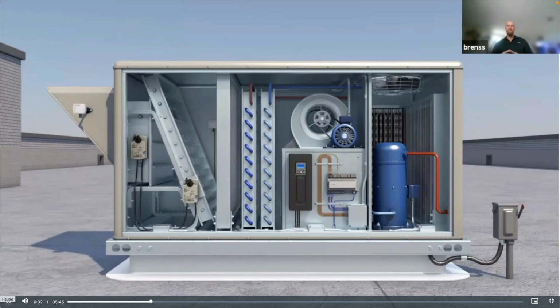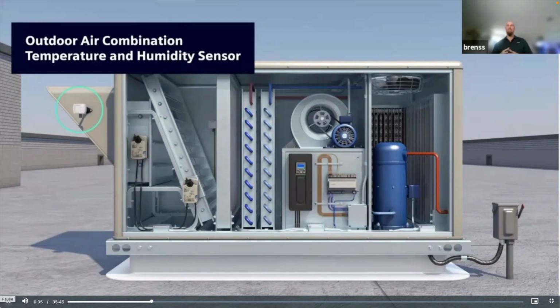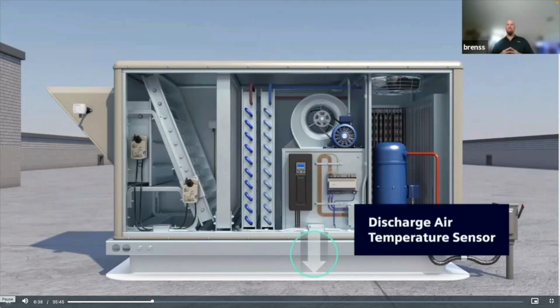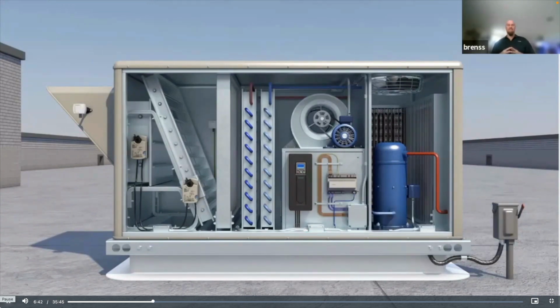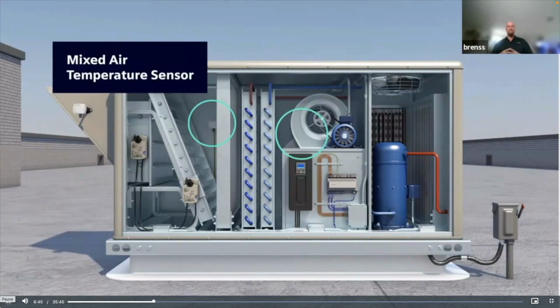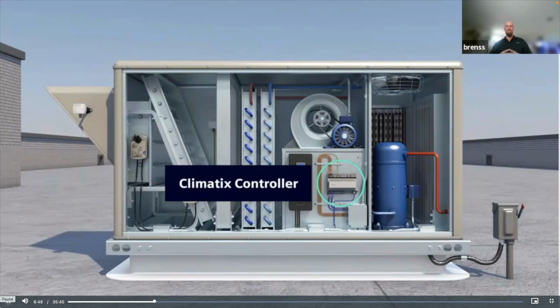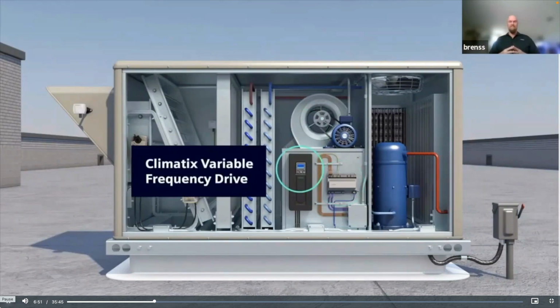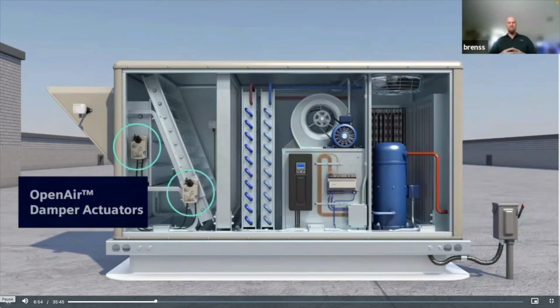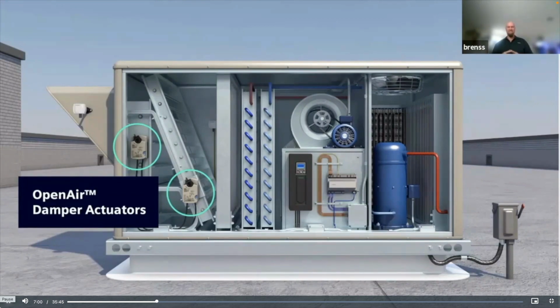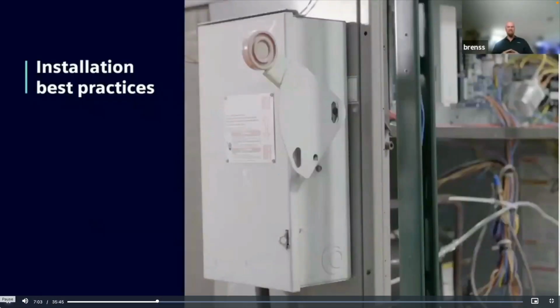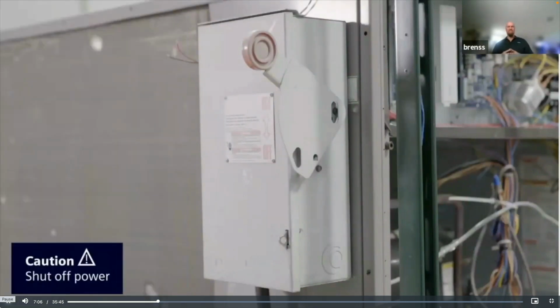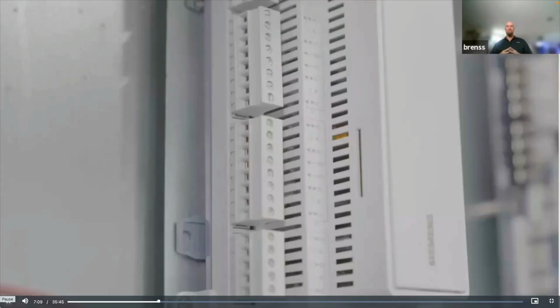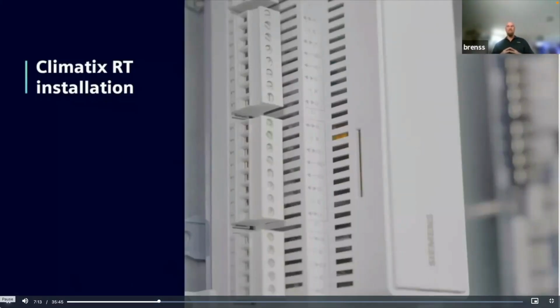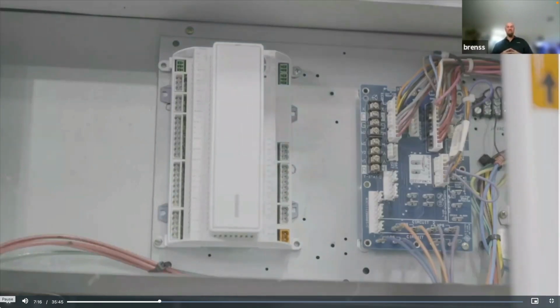Here are the mounting locations for the outdoor air combination temperature and humidity sensor, and the discharge air temperature sensor. Depending on the configuration of your rooftop unit, the mixed air temperature sensor may be located in different areas. The Climatix controller is located here, and this is the location of the optional Climatix VFD. Optional OpenAir damper actuators will also enhance the RTU's performance and energy efficiency with the use of economization. Before installation, make sure to shut off power to the rooftop unit. The Climatix controller should be mounted within reach of the PLC board in the control cabinet.